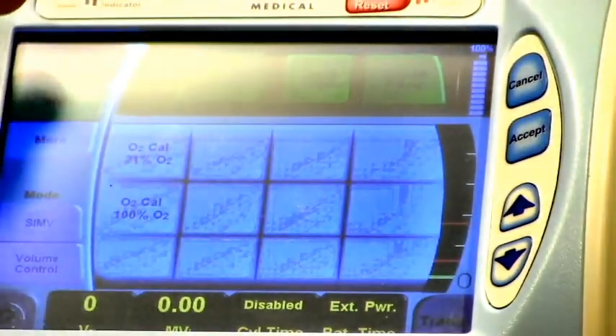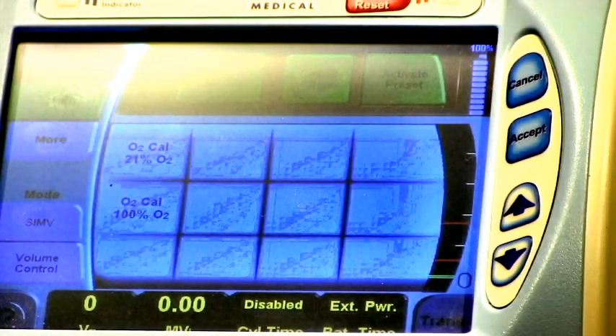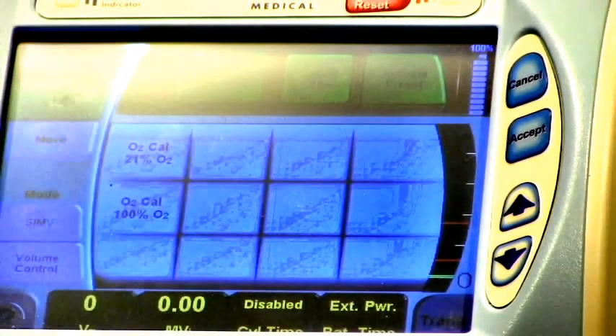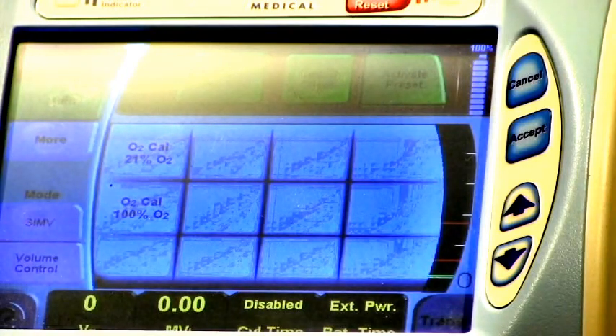When you calibrate O2, you have two functional calibrations that you can do. You can do a 21% FiO2 calibration and a 100% FiO2 calibration. Before you put the patient on, I recommend doing the calibration. You can do the O2 calibration at 21%. If you have the patient on and you're really worried about the amount of oxygen that you potentially may have in that cylinder, you need to enter in the appropriate amount of oxygen in the tank on the last screen, and then on this screen, you're going to want to enter in the calibration at 21% or 100%. I tell everybody, if you've already got the tank connected, do it at 100%.